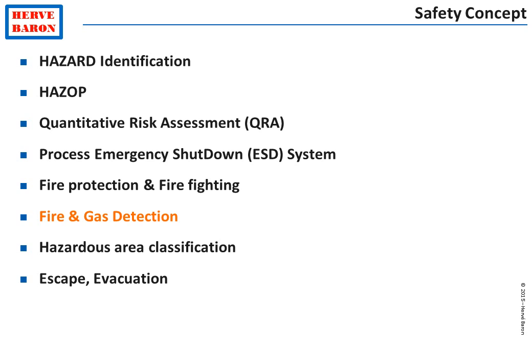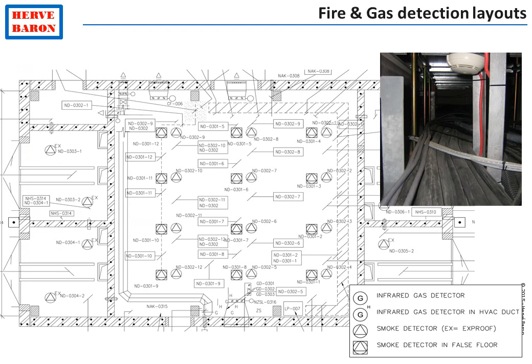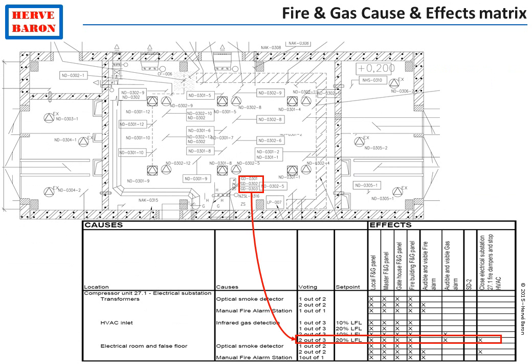Safety designs the fire and gas detection system. The fire and gas detection system gives alarm and executes automatic actions such as process shutdown, shutdown of building ventilation, and release of firefighting agent upon fire or gas detection. Detectors are provided throughout the process areas and within buildings. The actions initiated upon detection are defined by safety on the cause and effect diagrams. For instance, gas detection in the inlet ventilation ducts of a building is shown to stop the ventilation.